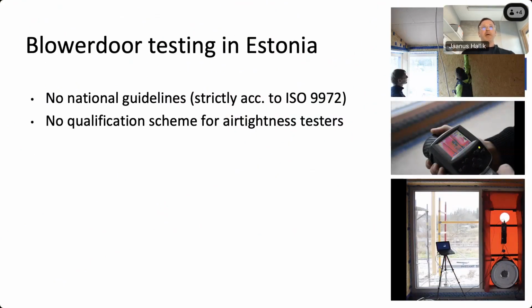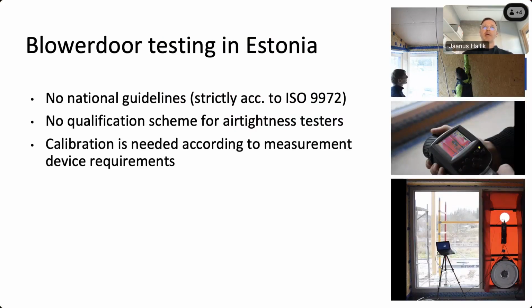What about the testing? There are no national guidelines, so the measurement is strictly according to ISO 9972. There is no national qualification scheme for airtightness testers, but the testing equipment has to fulfill the calibration requirements, meaning that the pressure measurement unit and all the blower door fans and equipment are calibrated within 2 or 3 years, depending on the system. You have to have a calibrated system to give out an official report of the air testing.